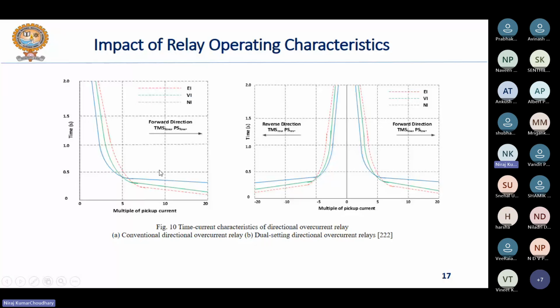So as you move away from normal inverse towards extremely inverse characteristics, you can see that the time of operation decreases. Means for the same magnitude of fault current, suppose the multiples of pickup current, that is in terms of current setting, is at 10, then for this particular value you can see that the time of operation for this red curve, which represents the extremely inverse characteristics, is the least, followed by the very inverse and then normal inverse characteristics, right?